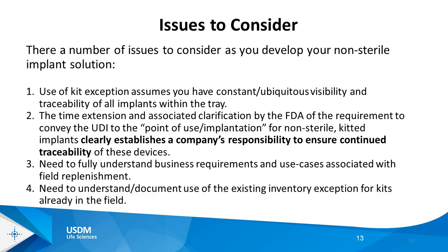Yeah, it's a great question, and it's a very interesting thought process. But if you stick with me here for a moment. So originally the requirement was we're going to direct mark implants, and recognizing that for various reasons that are described in 801.45, not all devices can be directly marked.